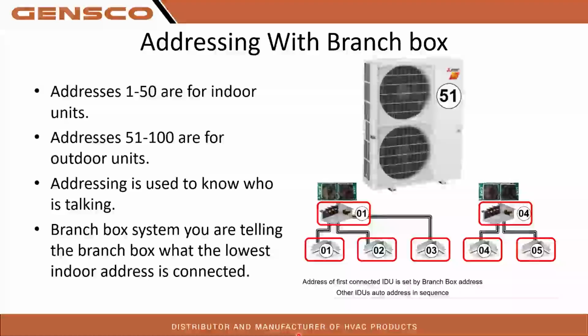How that address structure works is for your branch boxes, your branch box will automatically address all the heads connected to it, but you have to tell that branch box what is the lowest address connected to it. So for this, say for example, we have just a 1-to-1. My indoor branch box, I'm going to address it as 0, 1, because the first or lowest indoor address on that system is going to be 1. That way you're telling the branch box, hey, address 1 is on this branch box. It says, okay, I'll start addressing those ports A, B, C, D, whatever ports may be used. It just automatically assigns an address until either it sees a second address or it runs out of indoor heads.